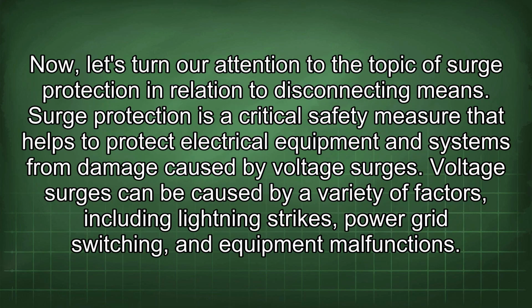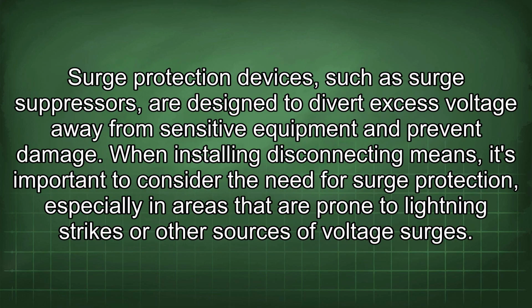Now let's turn our attention to the topic of surge protection in relation to disconnecting means. Surge protection is a critical safety measure that helps to protect electrical equipment and systems from damage caused by voltage surges. Voltage surges can be caused by a variety of factors, including lightning strikes, power grid switching, and equipment malfunctions. Surge protection devices, such as surge suppressors, are designed to divert excess voltage away from sensitive equipment and prevent damage. When installing disconnecting means, it's important to consider the need for surge protection, especially in areas that are prone to lightning strikes or other sources of voltage surges.